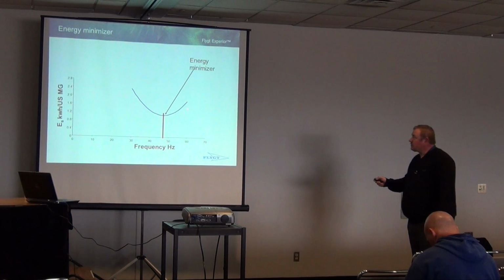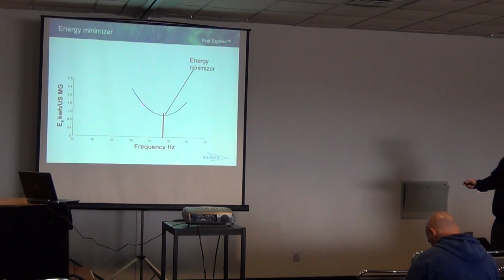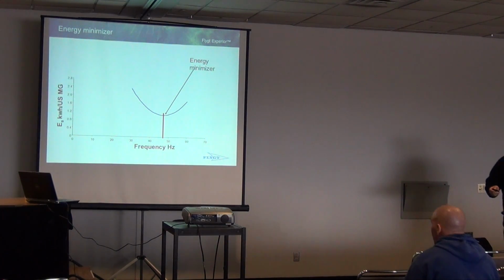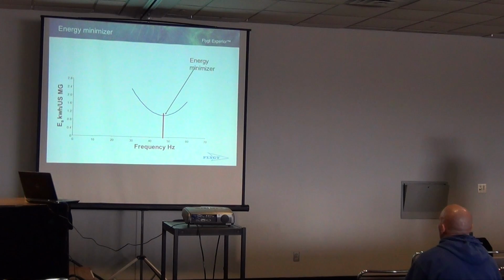We're monitoring specific energy the entire time on that station. As you slow a pump down one hertz at a time, you're going to get to a point, just less than 50 hertz in this particular system, where it finds the sweet spot in this specific energy curve. The minute that unit recognizes that if we go to the left and slow down some more, we start to rise in specific energy usage, it will correct and come back down into that sweet spot and settle in on the best spot on that curve, roughly 48 hertz. And it stays there. So in your normal day-to-day operations, it's going to ramp up, clean your pipe, and slow right back down to 48, because that's the best spot to save energy on your equipment.